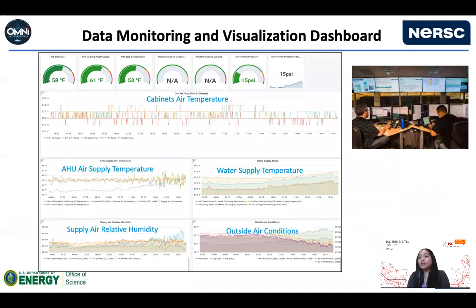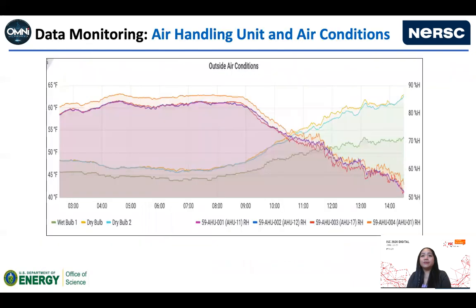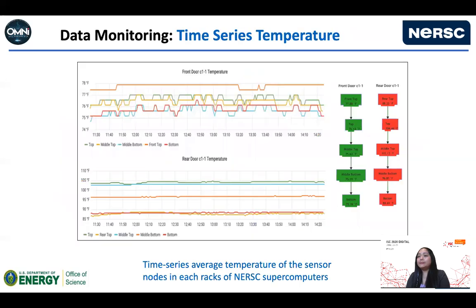This dashboard shows some of the critical values of the building management system, including cabinet air temperature, air supply, relative humidity, and water supply temperature. This dashboard shows the time series monitoring data of the air handling unit and the wet and dry bulb. The AHU controls the humidity of the facility, and the wet and dry bulb indicates how much moisture is in the air. Moisture in the air reduces the air temperature and lowers the temperature of the building, so less energy is used by the AHU.